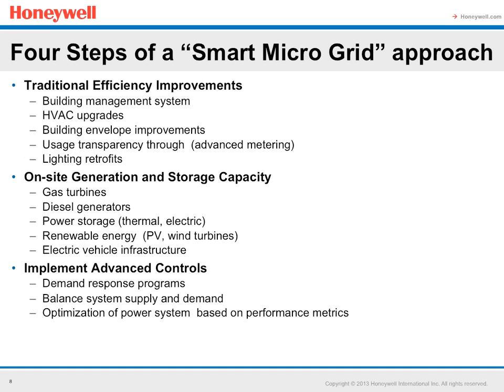Why do we want advanced controls? When you bring on the generation itself, you have to bring on loads to match as you begin generating power. If you bring on too much load, your power typically kicks out and you start over, so you want to control your load. You want to bring up critical loads first, life safety loads first—what do I need to make the campus run safely—then bring up the rest of the campus. That requires advanced communication between the microgrid and each of your buildings and overall campus.